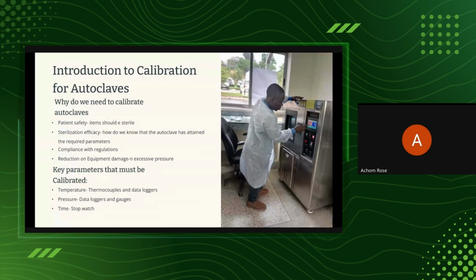Then the third parameter is the time. Remember we said if you're looking at sterilization time, you want to sterilize at maybe 30 minutes, at 25 minutes, at 15 minutes for drying, whichever. So we need to make sure that the timer is actually performing right. So we need to perform the calibration of the time.